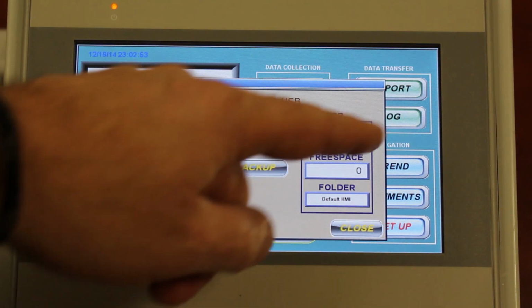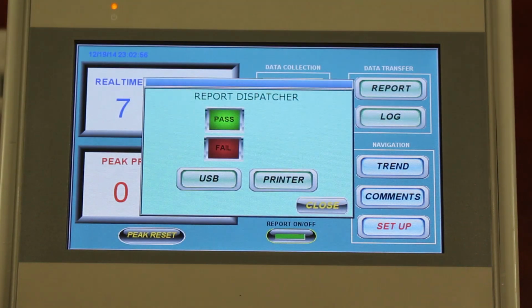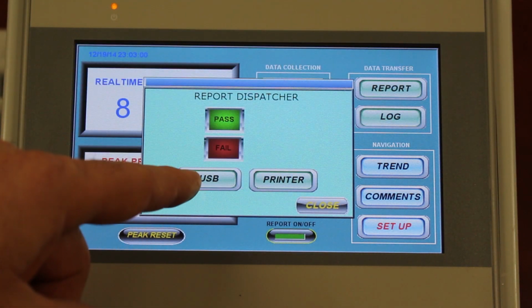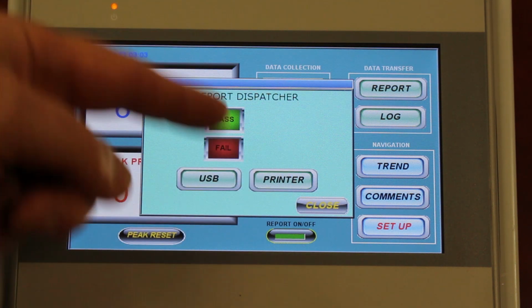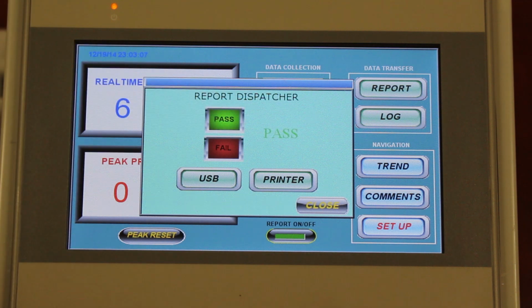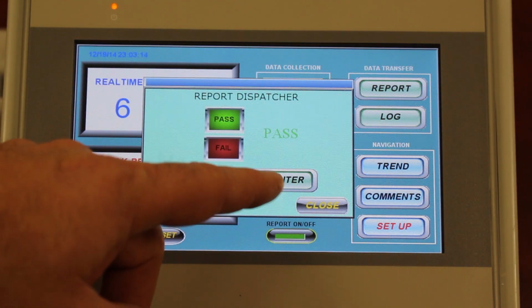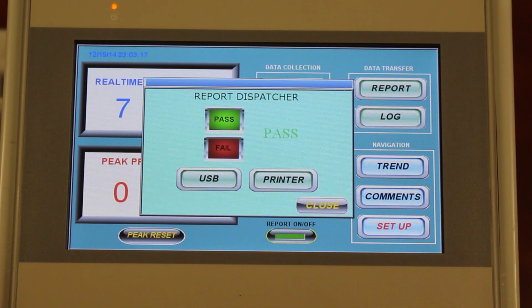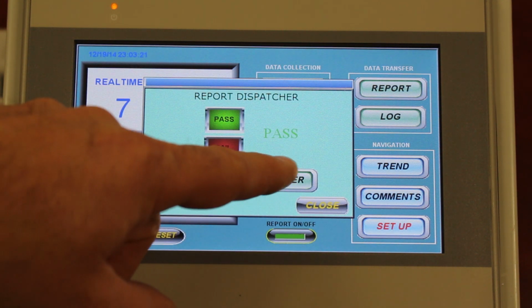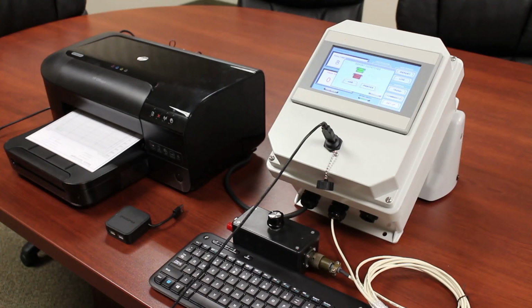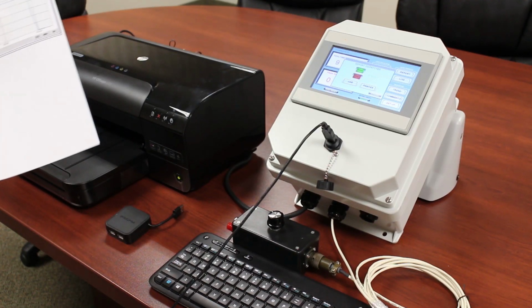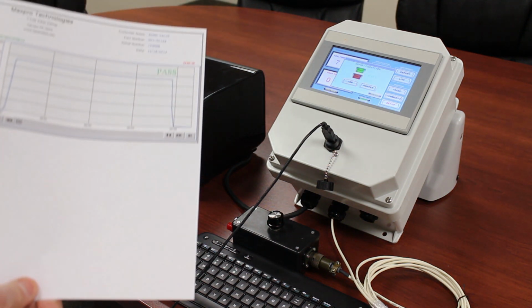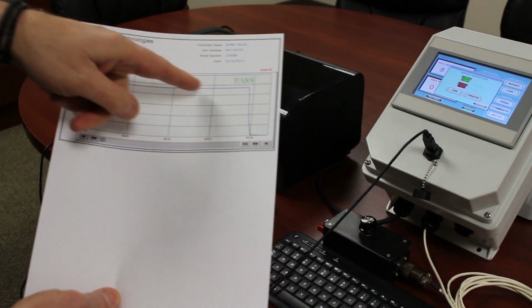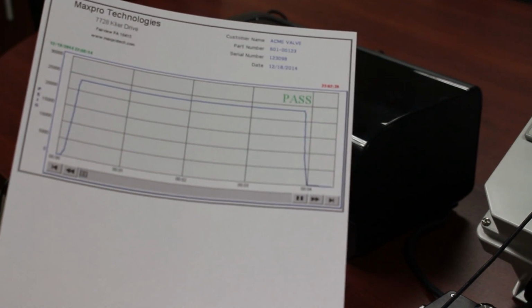So we'll go to the report screen. Gives you the option of sending it to a USB or to the printer. It also gives you the option to select pass or fail. So that will put a pass stamp on your test report. So the next thing we'll do is we'll hit the printer button, and that will automatically send your test report to the printer. And you'll see that it shows the pressure, the hold, and the letdown, the pass stamp, your company information, and all your customers' information there.